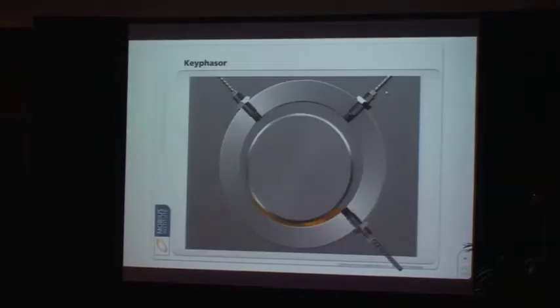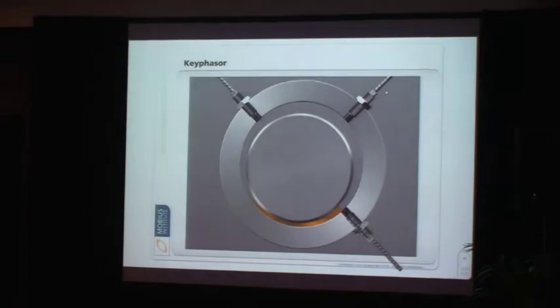So without going into great detail, we add a third probe, just one for the rotor, in a different plane, so it's not looking at the same point on the shaft as the other two proximity probes. It's looking at a keyway. As that keyway goes by, it sees a very distinct difference in displacement, and that's a timing signal we can use.